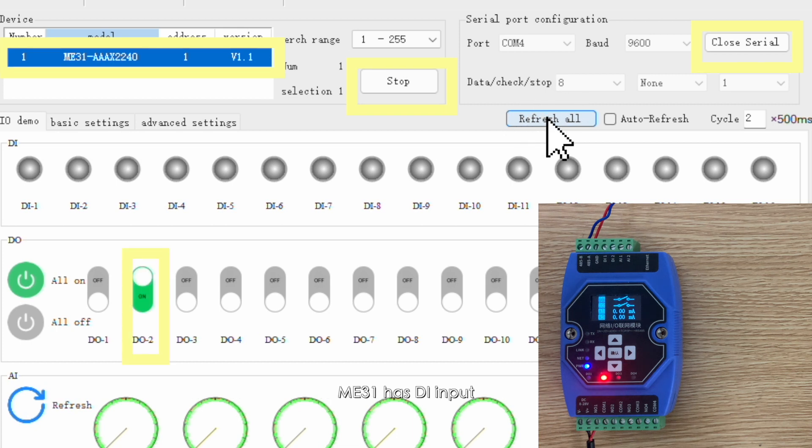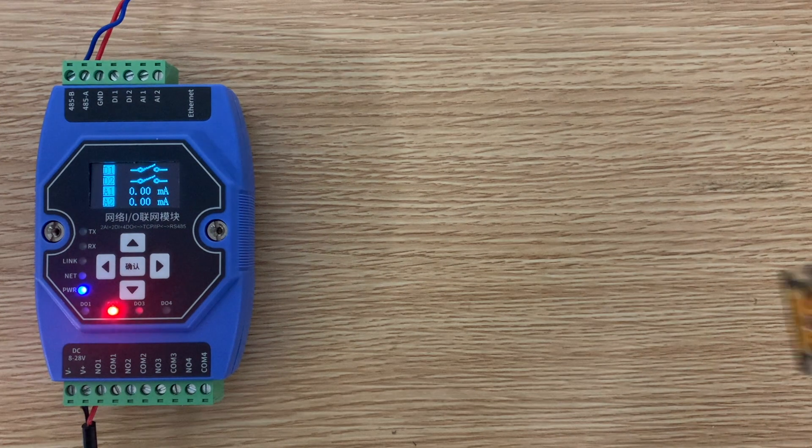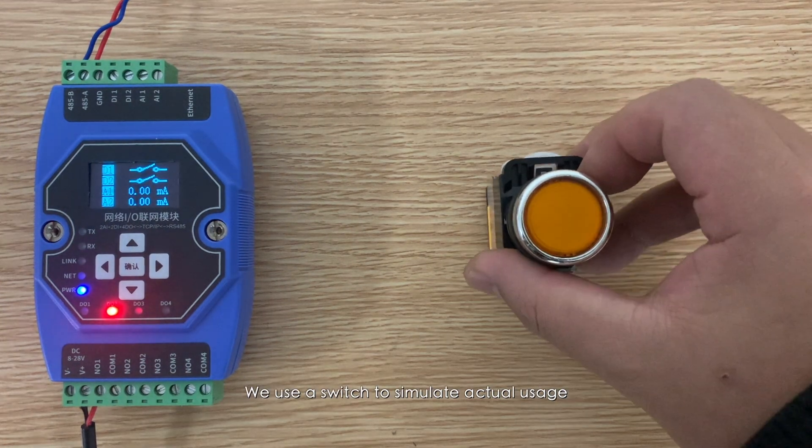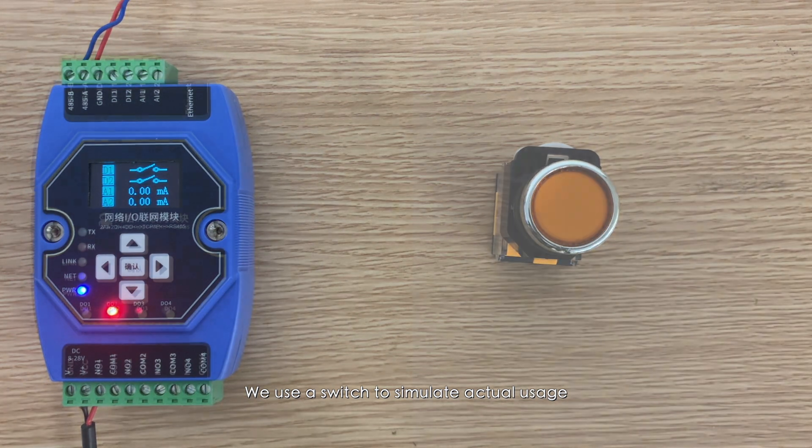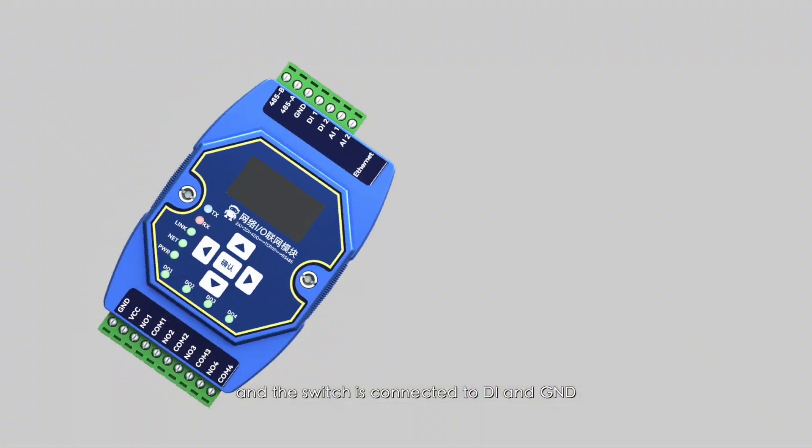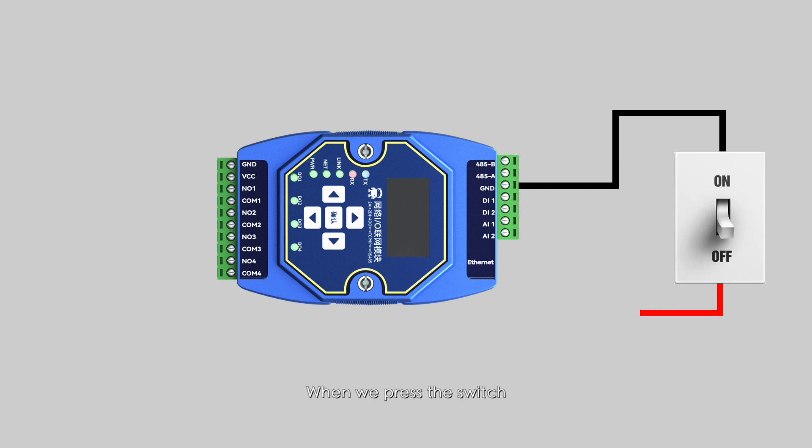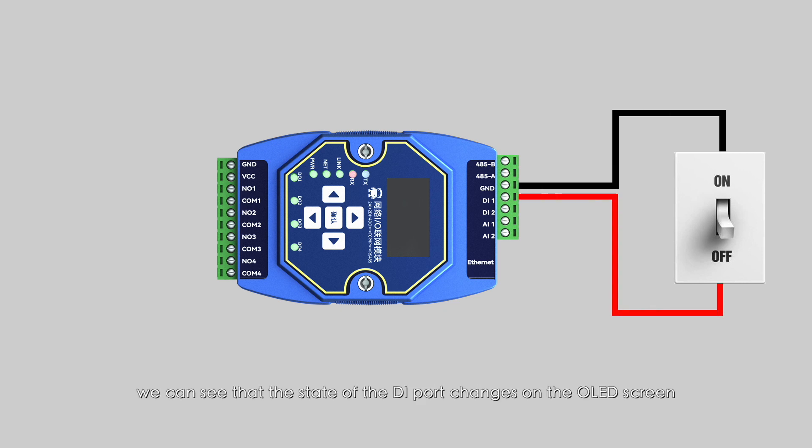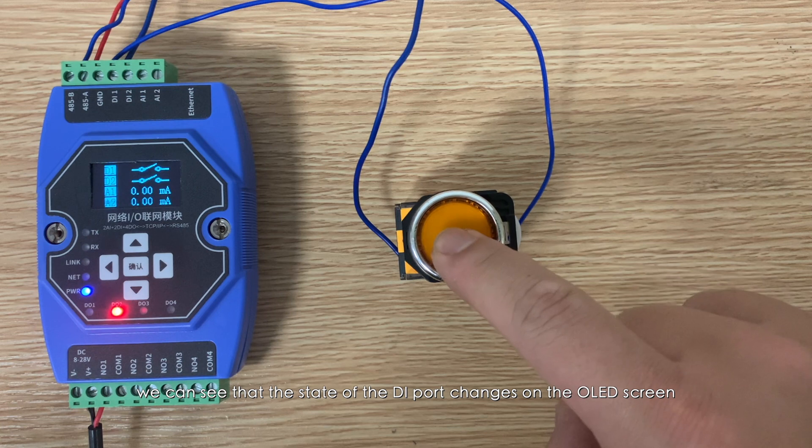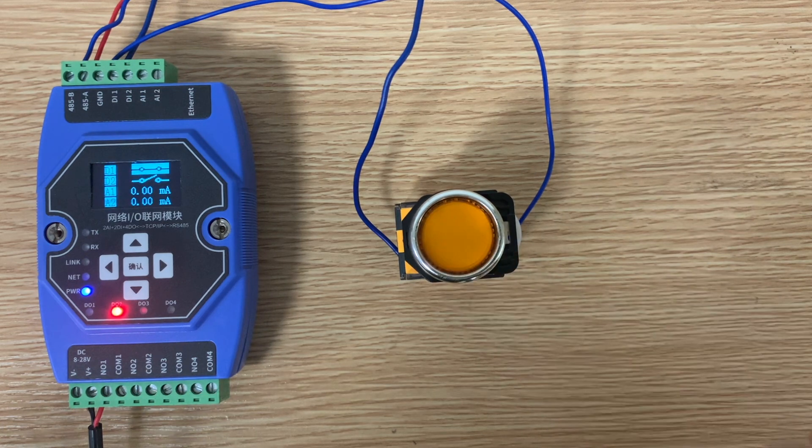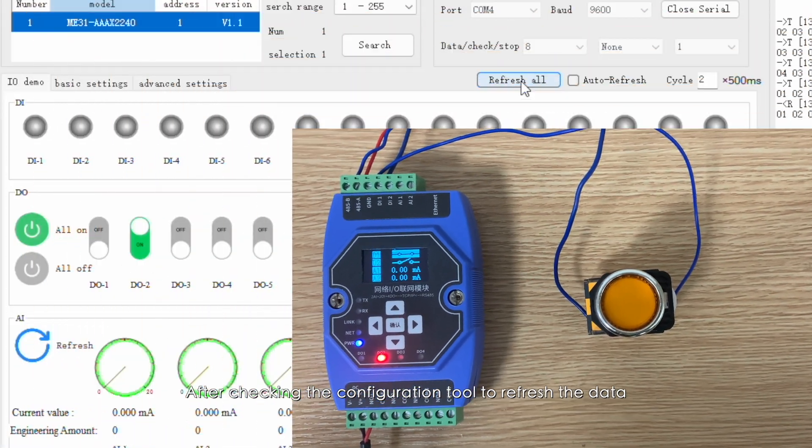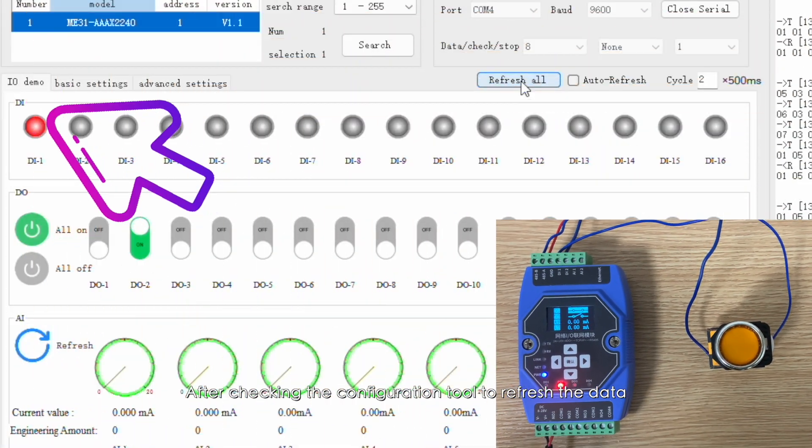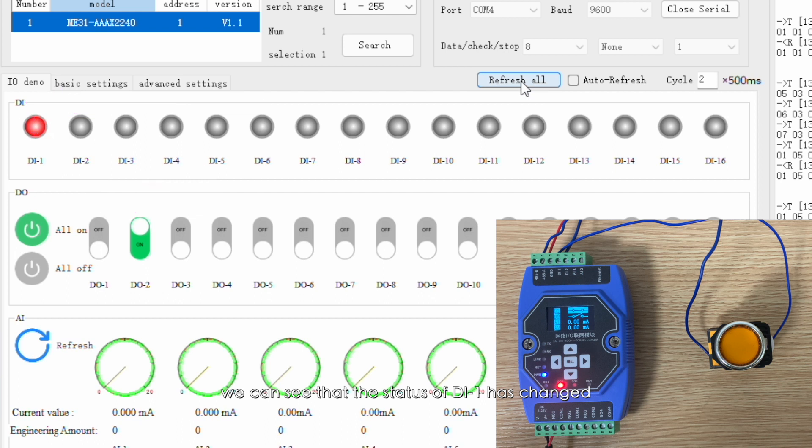ME31 has DI input. We use a switch to simulate actual usage, and the switch is connected to DI and GND. When we press the switch, we can see that the state of the DI port changes on the OLED screen. After checking the configuration tool to refresh the data, we can see that the status of DI1 has changed.